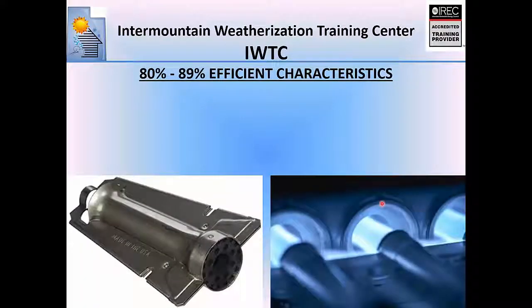Okay, all right, here's another thing you can look for. Remember the old ribbon style burners? Anything that's 80% efficient and higher is typically going to have these new in-shot burners, and they look like little jet engines when they're running. You won't see this on the older, what's classified as 60% efficient or anything under 80%.